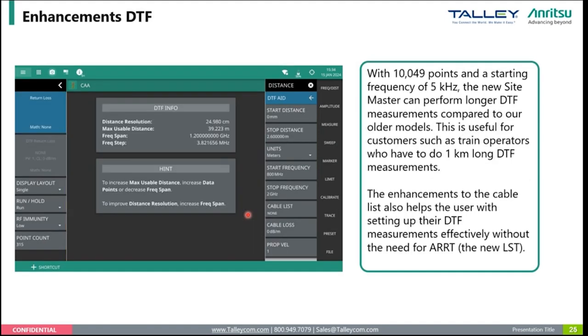When I say enhance, it's really a combination of multiple things together. Obviously, the more data points, the more accuracy and resolution you get. Starting at a lower frequency helps with that as well. So with all these things combined, and a better dynamic range, you're able to push the DTF further. You have more points to cover further distance, a wider frequency span, and a better dynamic range, allowing us to hear better during that signal.